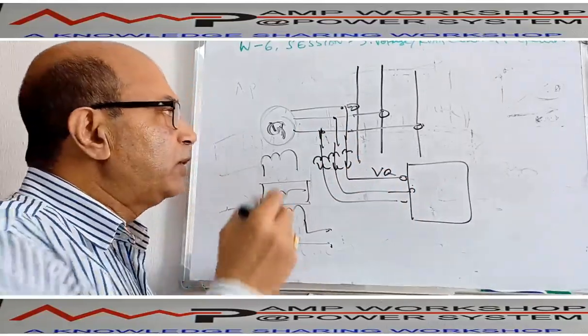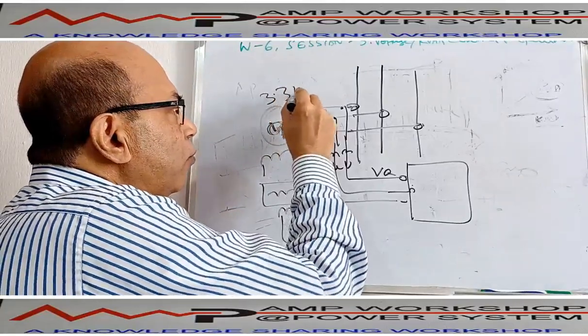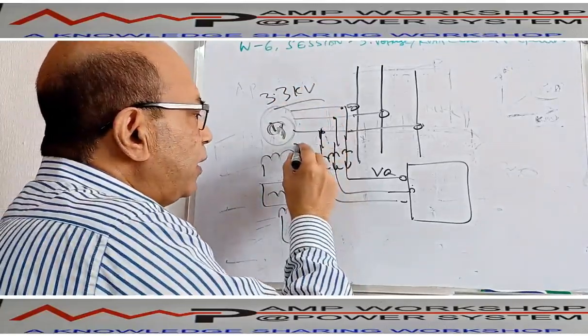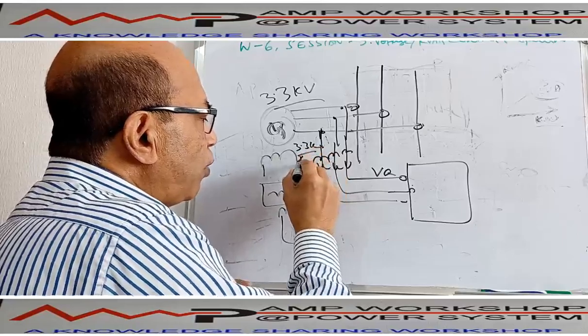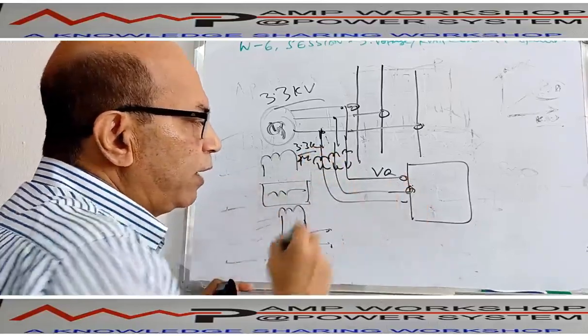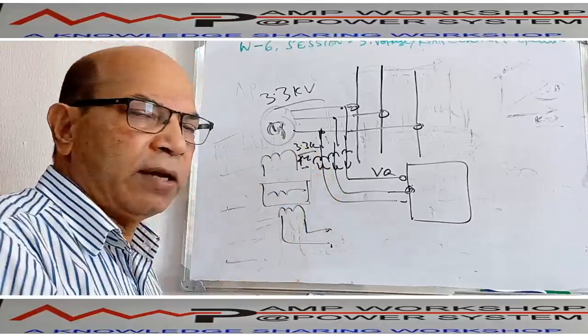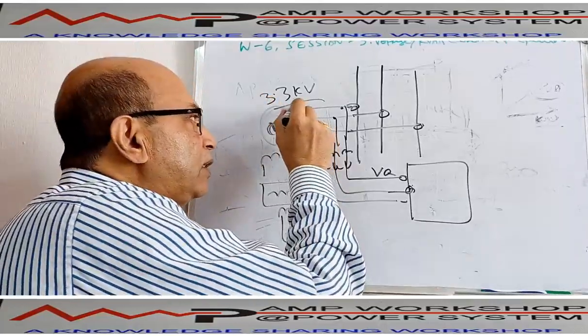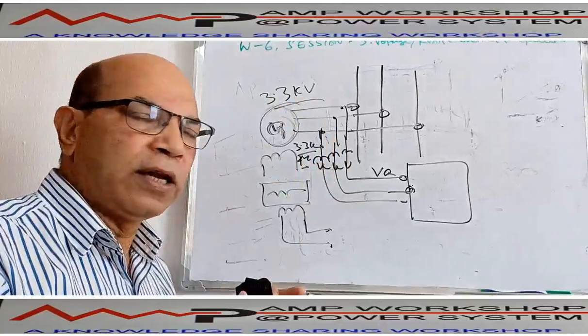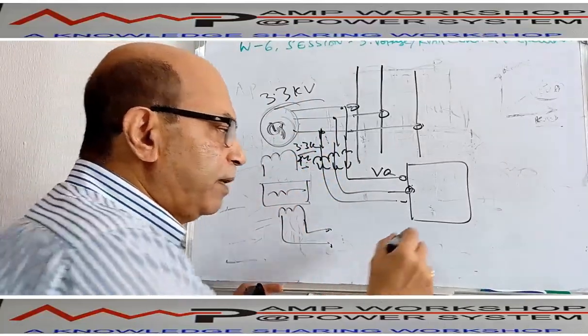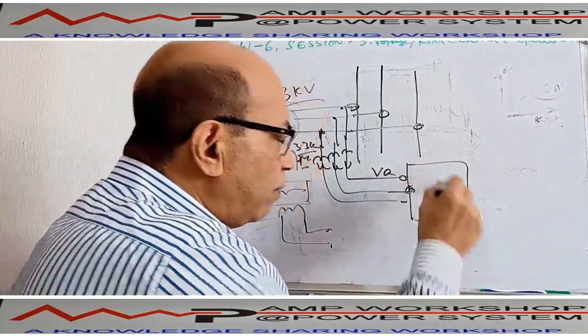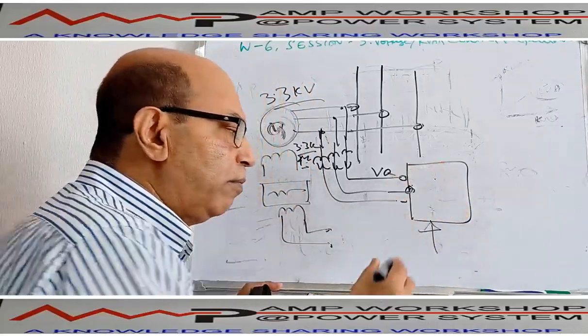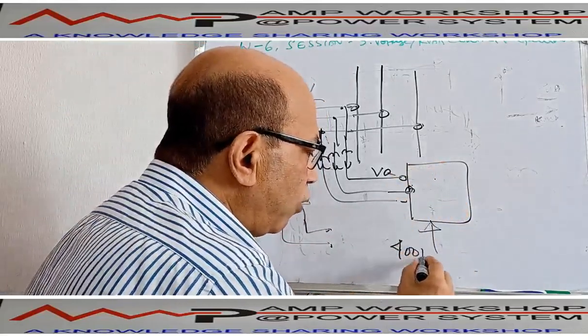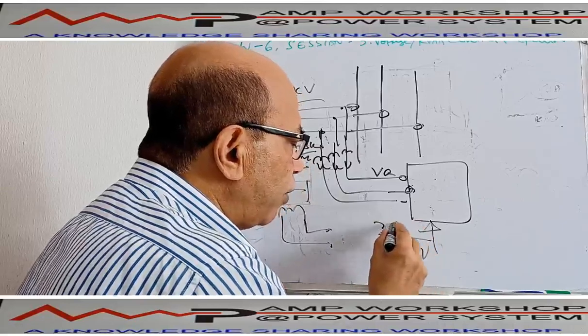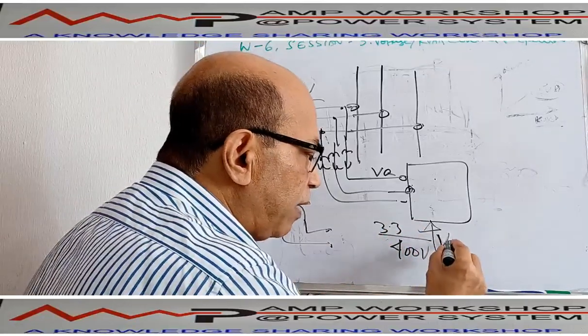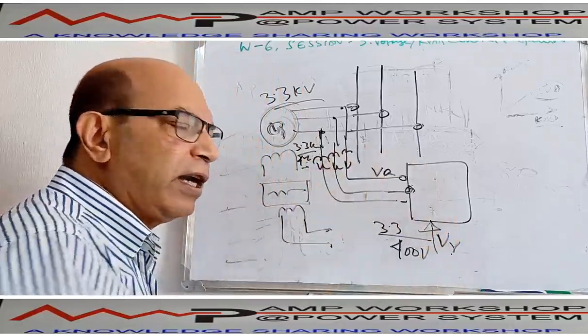And we know, suppose this is a 3.3 kV generator. We know that suppose this is a 3.3 kV by 400 volt PT. So input is 400 volt, that means 400 volt replicates 3.3 kV. Now we know this generator voltage, we want to maintain 3.3 kV, that is equivalent to 400 volt. That means there is a reference voltage already in the equipment, already informed to the equipment that I always need 400 volt input. That means 400 volt equivalent to 3.3 kV. So this is my reference voltage VR. This reference voltage is already given there.